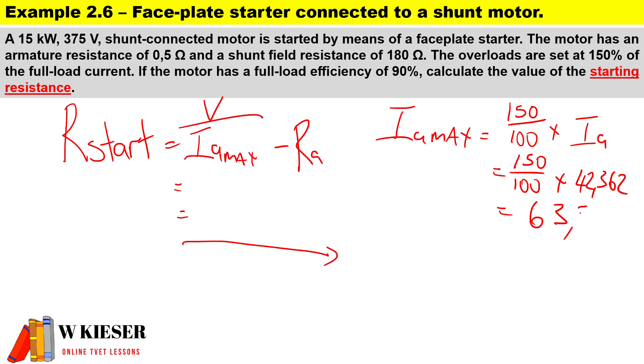Now that we've got Ia max, we can actually calculate the value of the start resistance. The terminal voltage is 375 divided by Ia max, 63.543, minus the armature resistance, which is the smaller resistance of 0.5. Therefore, the value of the resistance connected in series with the armature will be 5.402 ohms.